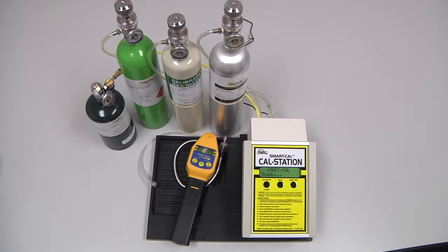To perform an automatic calibration of the Gold 100, we will need the instrument itself, the cal station with instrument hose, and the calibration gas with regulators and cal adapters.